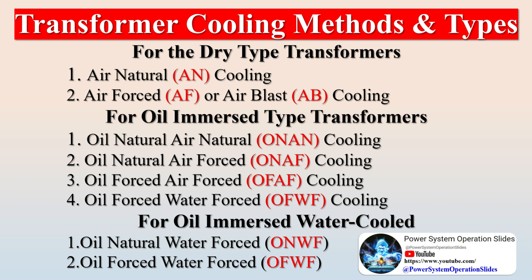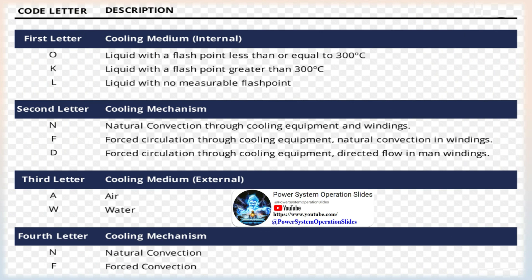Dry type transformers are cooled by air circulating over the outside housing. These transformers are usually rated no higher than 500 kilowatts. Dry type transformers are commonly wall mounted and used for lighting. Unlike oil immersed transformers, they may be used indoors without a fireproof vault. Dry type transformers have two further subtypes: Air Natural and Air Blast (Air Forced).